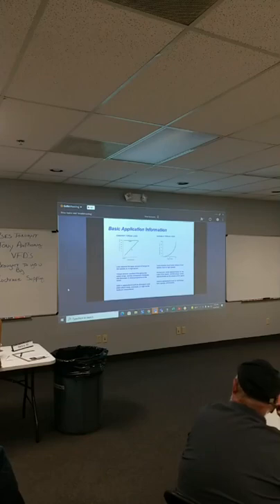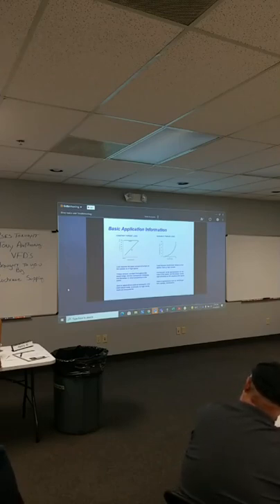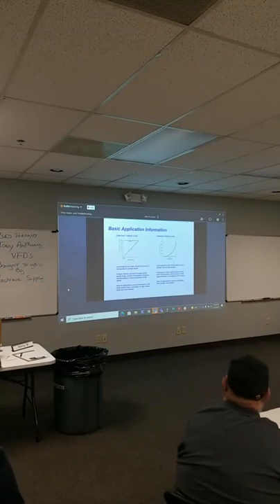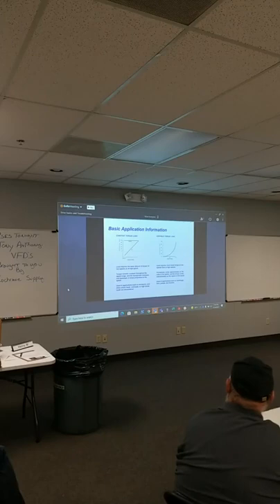Well, we get the question all the time, hey, can we run that motor at 70 hertz to get a little more flow, a little more air? Depends. Once again, a little change in speed up here is a huge change in power, which is a huge change in current. You may overload that motor and overload that drive at 70 or 75 hertz. You also need to look at your fan curves or your pump curves. But there's a certain point going up there on that variable torque curve, where it might be 70, 75 hertz, where all of a sudden that torque is building, building, building, then it drops off to almost zero.